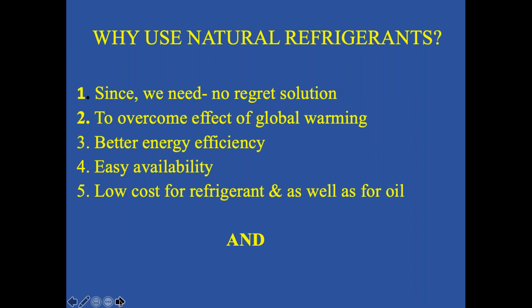Now, besides this, we go to some thermodynamic properties and go into a little more detail. So, what are these? A high latent heat of vaporization. Now, we need to understand the meaning of it. See, it is the latent heat which makes the refrigeration or air conditioning industry work. For example, in the evaporator and condenser, when we say evaporator, the liquid refrigerant evaporates, and the refrigerant which has higher latent heat will give better results. So any refrigerant should have as high a latent heat as possible. Then it is a better refrigerant.